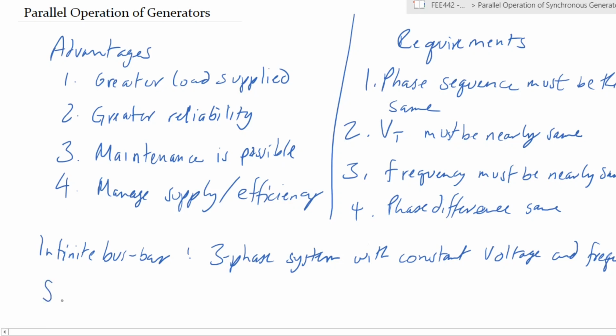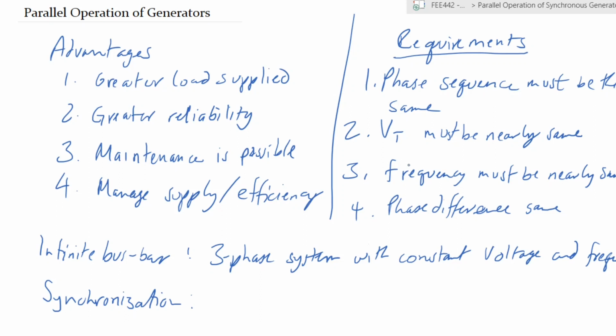The other concept that we want to introduce is synchronization. Synchronization is the adjustment of the speed and frequency of a generator when it is being connected to a system. In order to achieve synchronization, you need to meet all the requirements that we have listed here. When all these requirements are met, the generator is said to be synchronized to the system that you want to connect it to. And like we said, a system can be another generator or a set of loads or even an infinite busbar, which is the equivalent of a national grid.